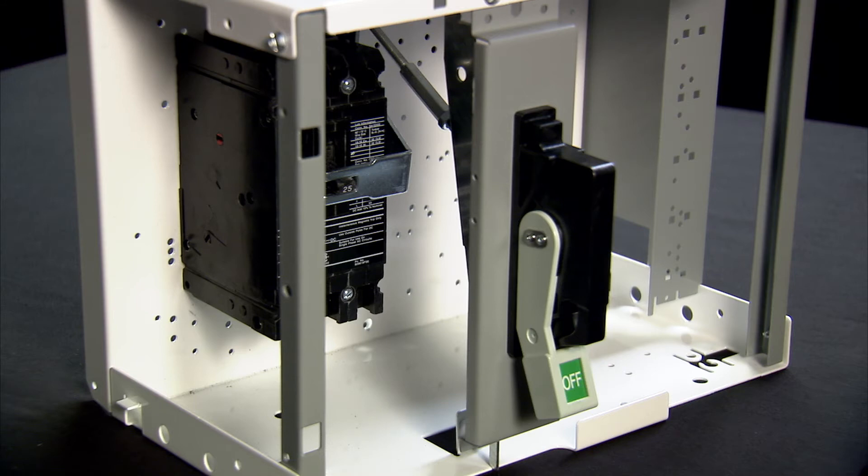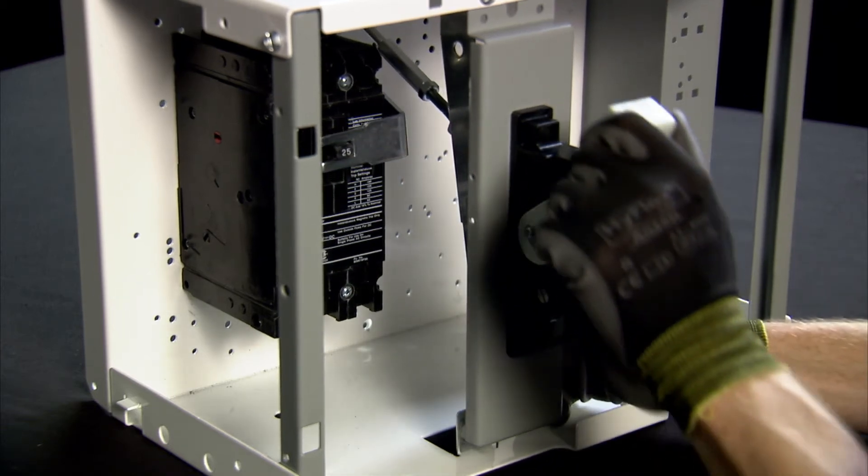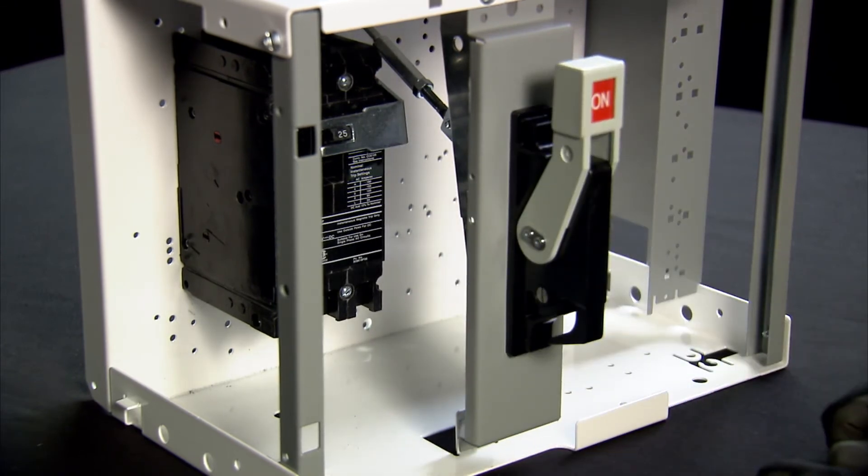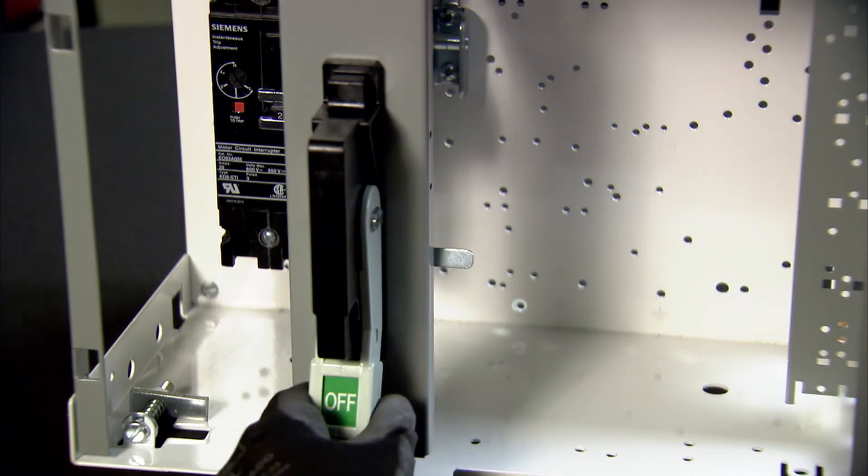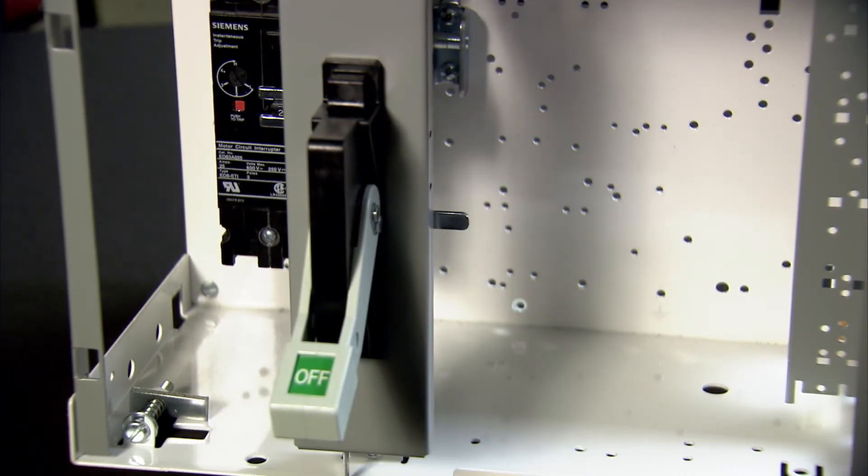Before making any adjustments to the handle, remove the unit from the motor control center or put it in the test position. The handle is properly adjusted if moving the handle from the off to the on position switches the breaker into the on position.